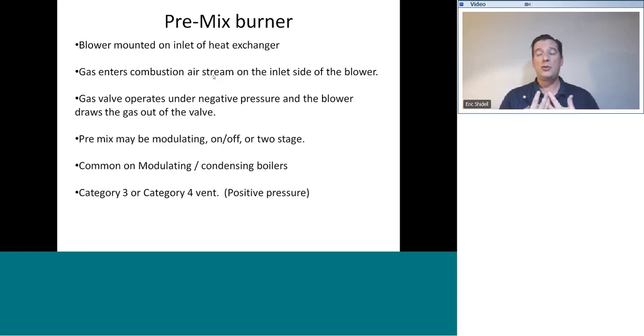Our premix burners may be modulating, like I said, or they may be on-off style, or they may be two-stage. The on-off style and the two-stage burners are going to be found on very large commercial boiler style appliances, such as a Patterson-Kelley boiler or a Camus boiler. Those are also Raypak modulating vertical boilers that use a premix burner as well. So those are some very large capacity, multi-million BTU input boilers. Small footprint though, they'll still fit through a doorway, kind of neat.